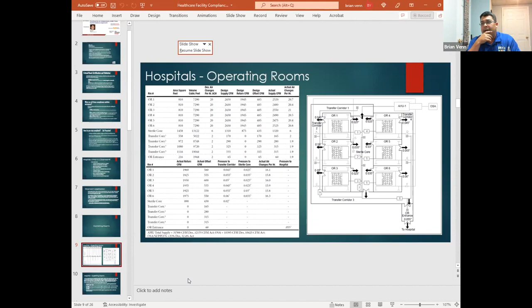There should be a map showing the space and the relationships to the corridors, as well as the directional pressurization with the arrows. Again, with the new ASHRAE 170 standard, the update of the actual values being written with the arrow is relatively new, and it allows us as test and balance professionals to go and achieve that goal, rather than maybe set it up with a directional of 0.01 and we think that that's okay, but the owner and the engineer would have liked to have seen a 0.025 to have a little slop in the pressure at those doors into the sterile corridor. Now with that new standard update, which is really the most important change in the 170 standard for us as TAB professionals, it really does give us better direction on what to set these rooms for.